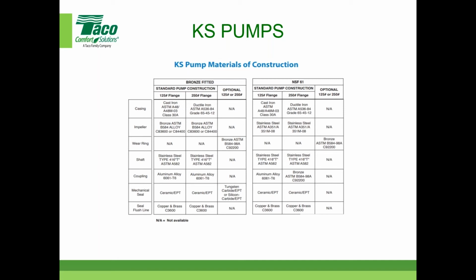And then the couplings, and our standard seal is a ceramic EPT, pretty common. It's a John Crane type seal, but we do have some other options there, and we actually have some others that are listed, or your Taco rep can get you some more information on that. And we do have that flush line that we feel is very, very important to keep that seal flushed, so it flushes away any grit that gets into there, because seals do not like grit or grime or anything like that.